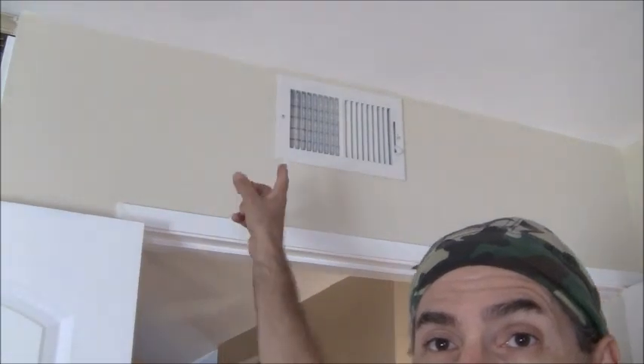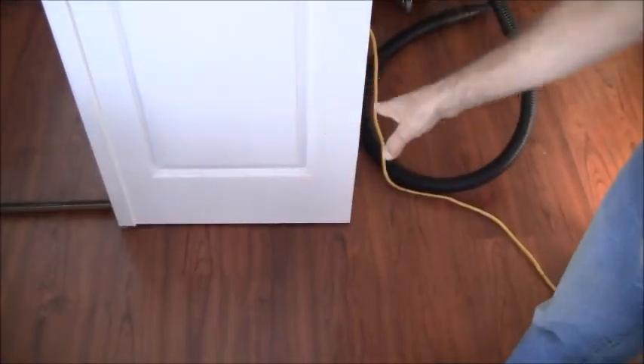When the AC contractor did the original job, they put the supply registers towards the doors of the bedroom. So right now we're in one of the bedrooms on the 2nd level. Personally, I don't think that was a good installation. I think it would have been better had they installed the supply register closer towards the window exterior wall, and then allowed the return to either come through the open door or have the door cut, so it would come underneath the door for your airflow in order for the system to breathe.